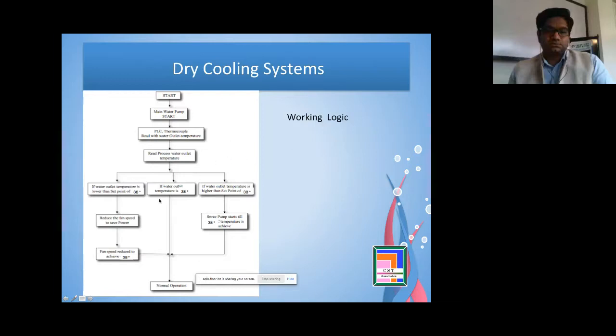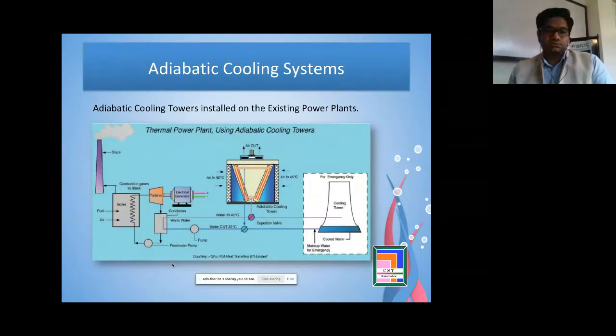So now let's say the water temperature is more than 38 degrees centigrade. So what happens is, excuse me, the water temperature is like 45, 46 degrees centigrade. So our spray water pump will start, and then it will bring the temperature to 38 degrees centigrade. So once that becomes 38 degrees centigrade, then it will further see if there is any scope of reducing the quantity of water or the quantity of air. In both cases, there is a benefit: either we save water or we save energy, which is in the form of electricity.